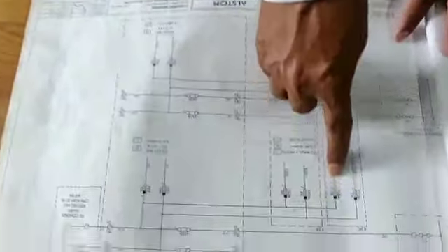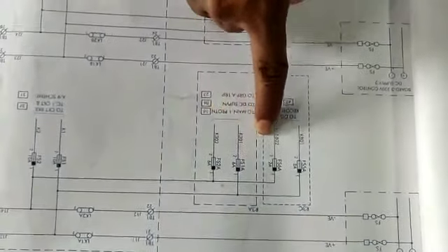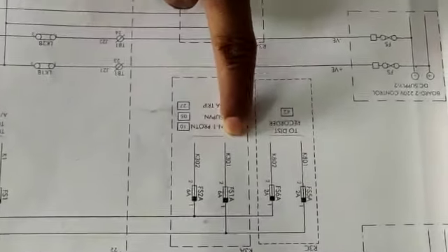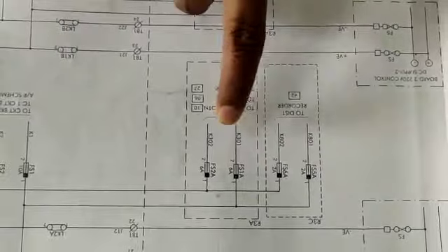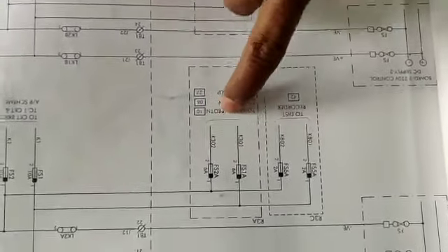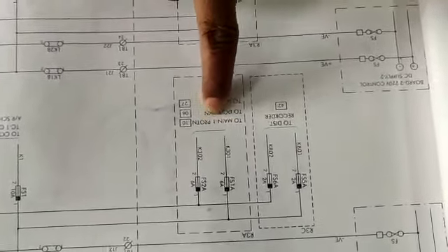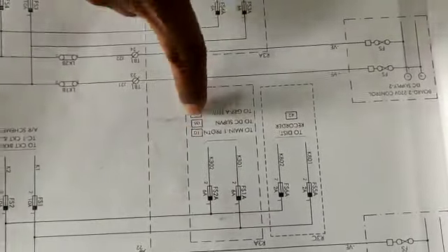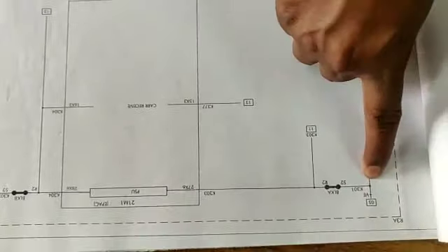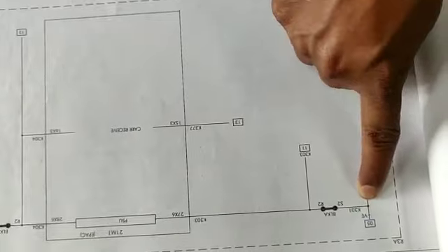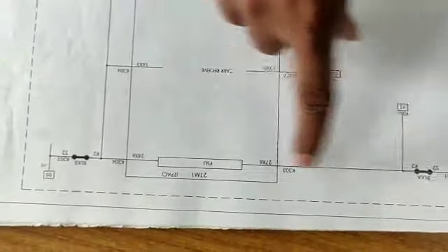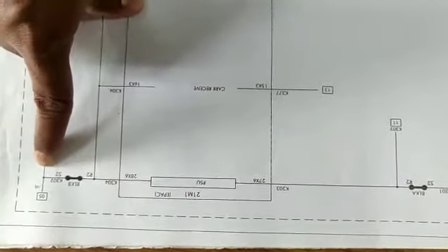Now if you look at this page, this is K301. K301 means it is a control DC supply, or DC supply for controlling purposes, and controlling for which? Controlling for main 1 protection. Now you go to page number 10. This is page number 10. K301 coming from page number 5 is connected to the power supply unit. This is positive. Similarly for the negative side also.